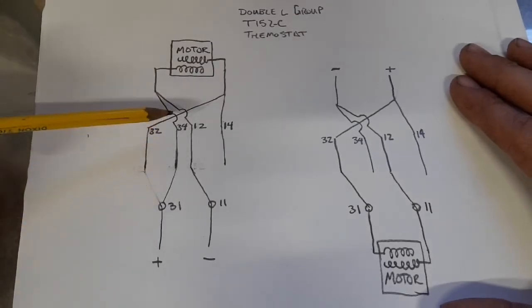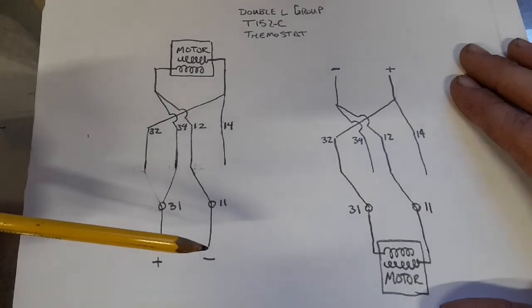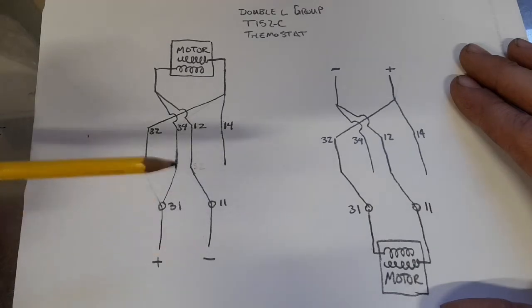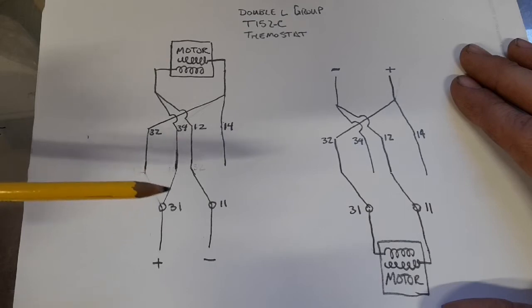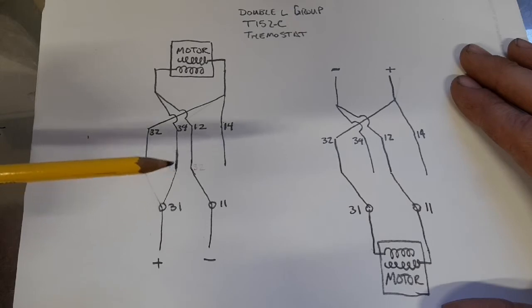So, my positive path comes up, comes to where they're tied together, and then comes back down and causes a short in the transformer. What happens is that these switches that go back and forth, when they get shorted out on that 24-volt transformer, it actually causes them to stick on the inside.